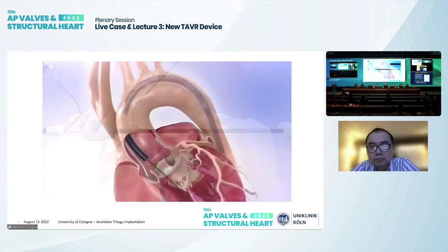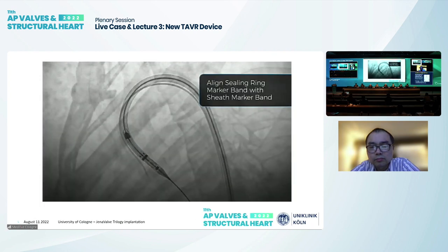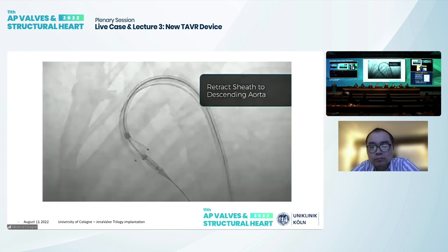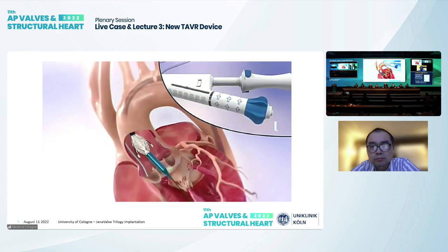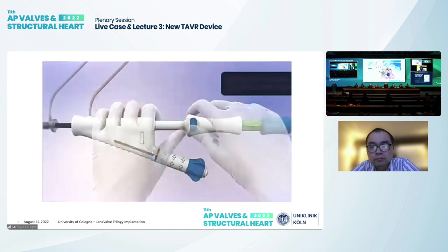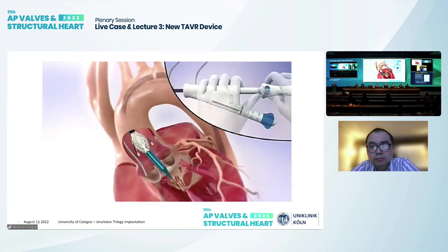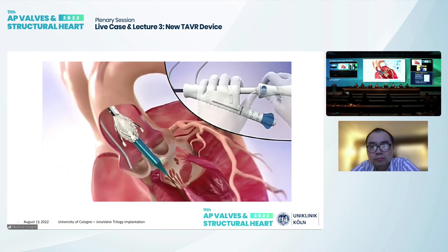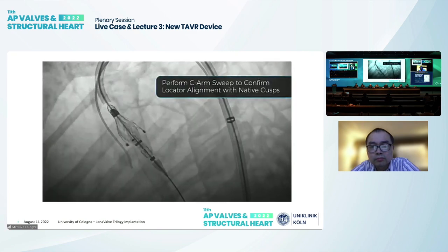So advance the delivery catheter, as you see here, and then align everything and then remove the sheath. And by that, we will expose, as you can appreciate here, these three locators. You can then flex the system to get a little bit more central and then advance the system with that two blue button mechanism.